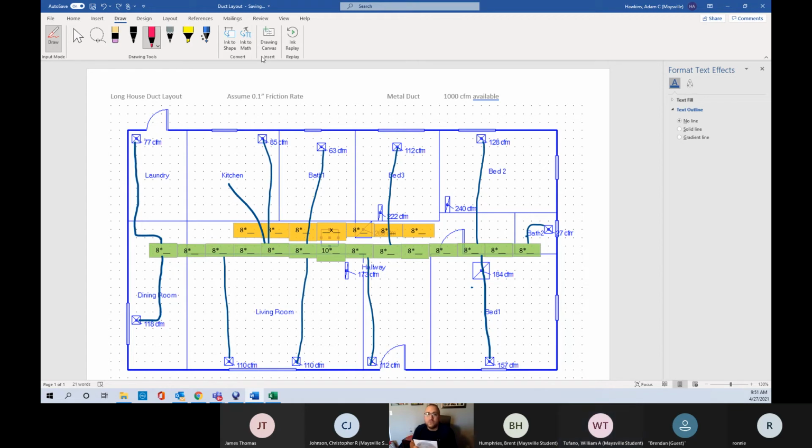No. Imagine you're blowing through a straw, a little small straw, and you blow as hard as you can, or through a little bitty hole. Your cheeks are going to puff out, right? That's static pressure. That's back pressure. Oh, it makes it quieter, doesn't it? Yes. Once it gets through there, you're going to have a lot of velocity, right? Noisy, loud. You're moving enough air, but at the harm of noise. You're losing quietness.